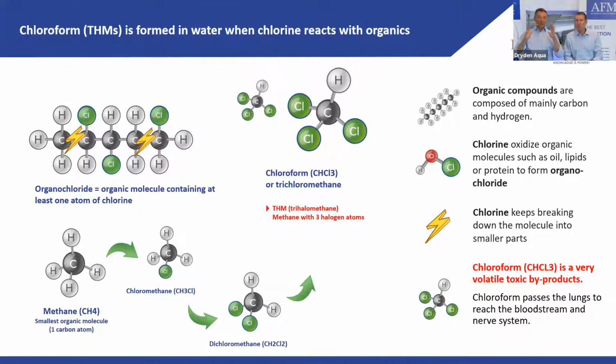You heard about this different times. We are really brainwashing you here because it's really important. And what does it mean? If you reduce more organics by better filtration, talking about AFM, if you reduce 50% more organics, you have 50% less chloroform or other THMs. So here AFM brings such a big value, and chloroform is important.